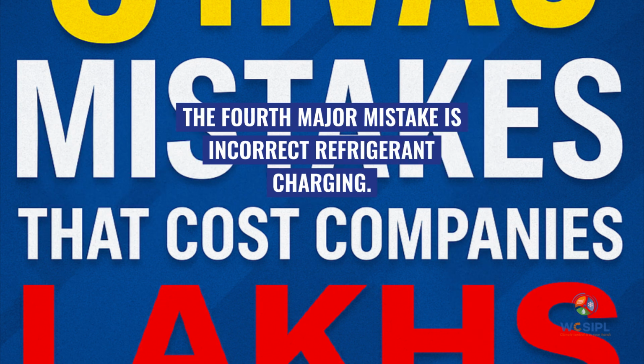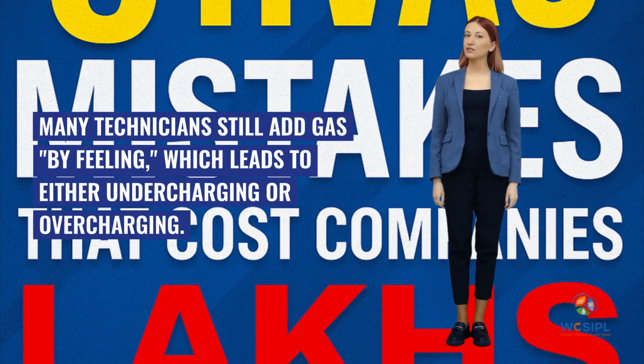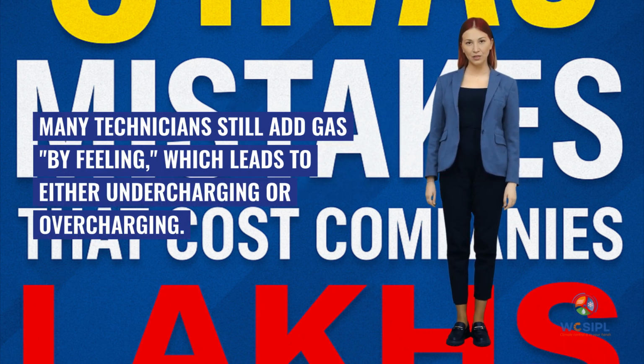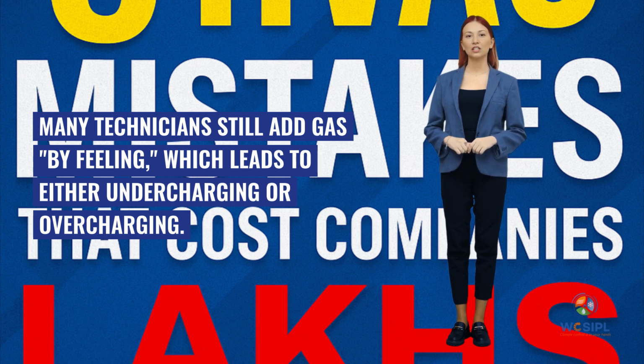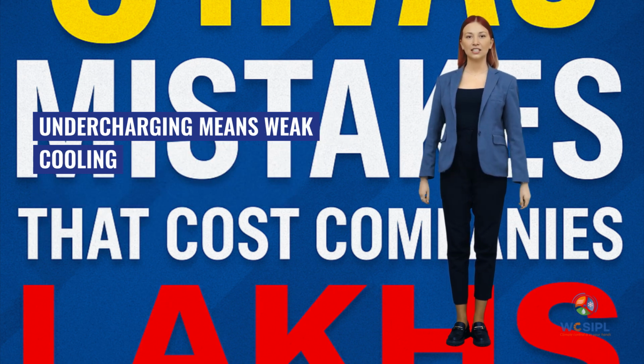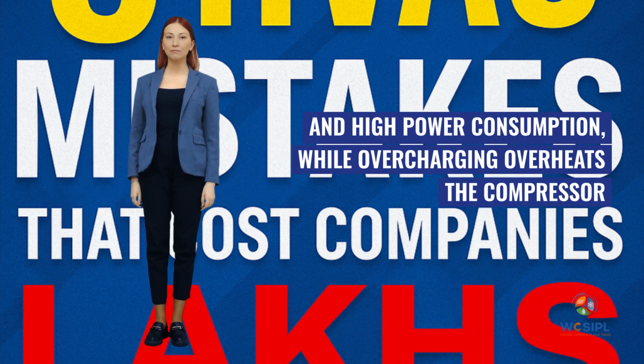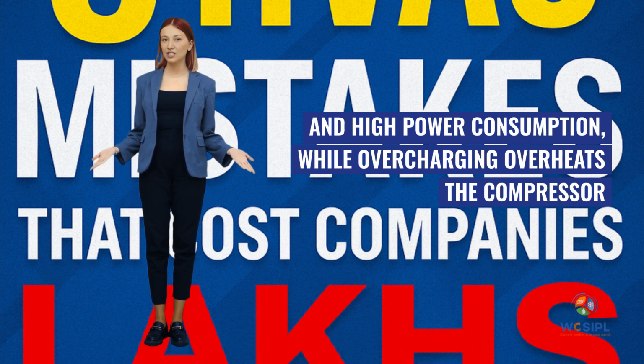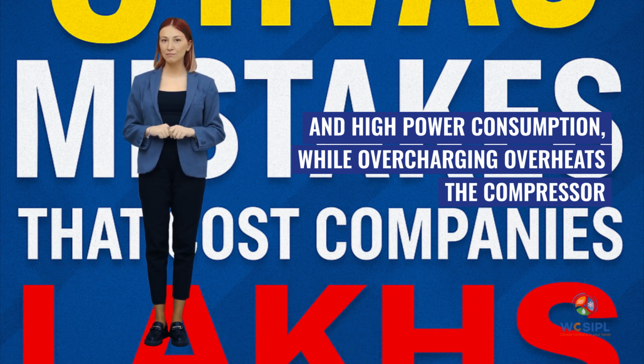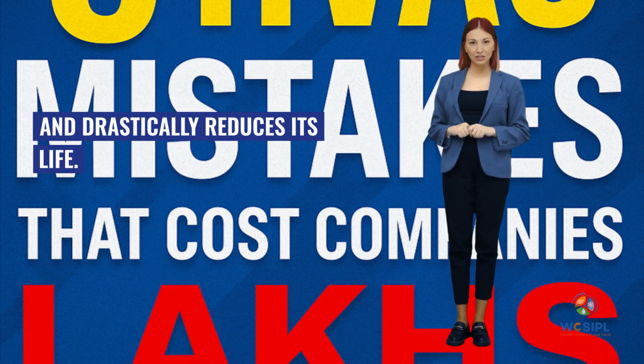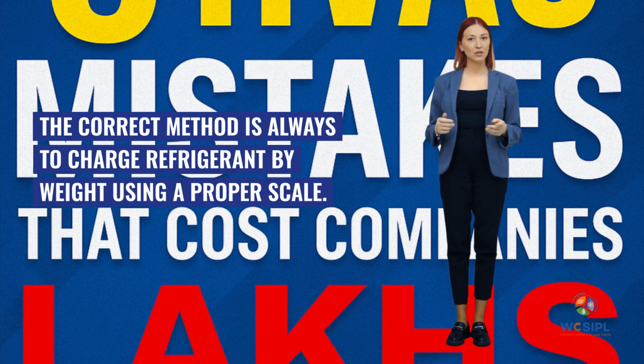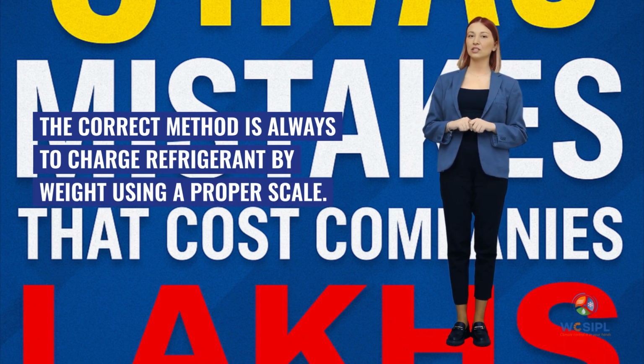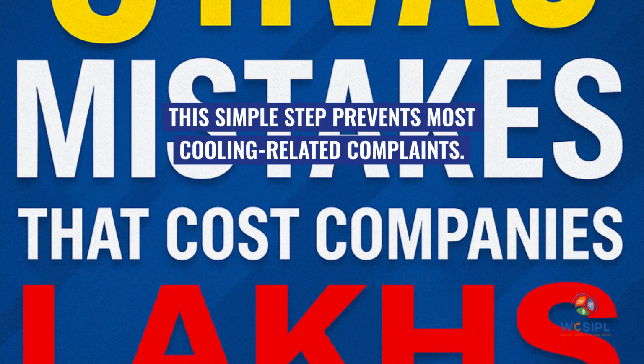The fourth major mistake is incorrect refrigerant charging. Many technicians still add gas by feeling, which leads to either undercharging or overcharging. Undercharging means weak cooling and high power consumption, while overcharging overheats the compressor and drastically reduces its life. The correct method is always to charge refrigerant by weight using a proper scale. This simple step prevents most cooling-related complaints.